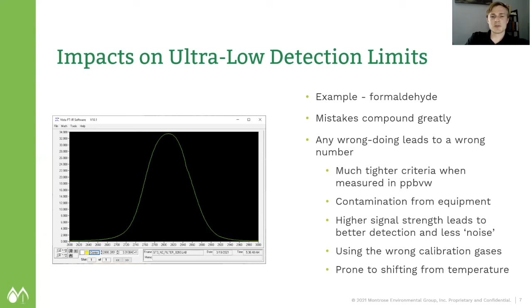It all goes back to understanding the methodology, using the correct calibration gases, avoiding span factors. You do not span your CTS. That's a big no-no that we have seen. And understand how sensitive these instruments are. Ambient temperatures really dictate the health of the instrument in the field. In a perfect world, you'd be in a 75-degree Fahrenheit room with no wind, nothing, but we do stack testing. So you're going to be in a trailer, potentially 100-degree day with AC units struggling to get cool. So you're going to see some swings.